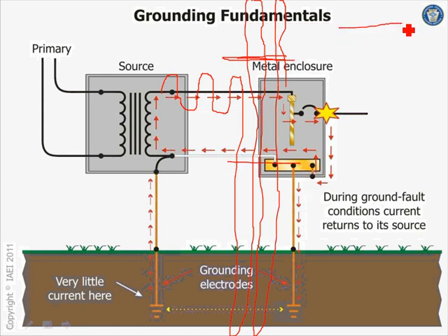Here's my phase A, it will be taking it to, here's phase B, typically, and here's the surge protector or surge resistors, sitting like this. Now when the voltage goes very high on that line, this will jump and basically ground your phase, sucking that energy into Mother Earth. In the process, it will save your fire alarm system or electronic system and so forth. Applications use the same thing a lot of times outside.